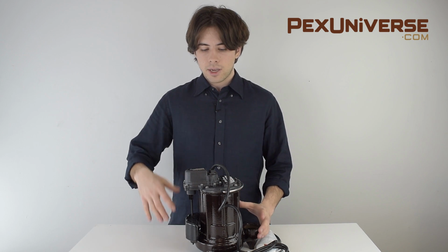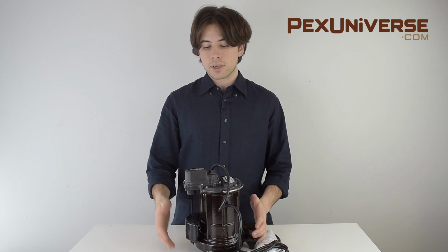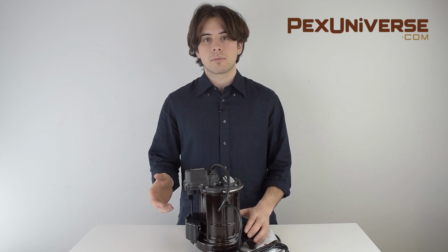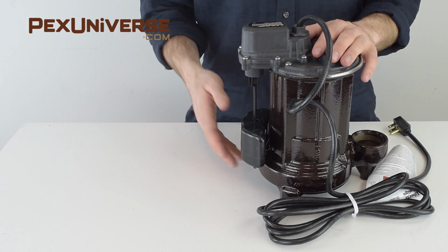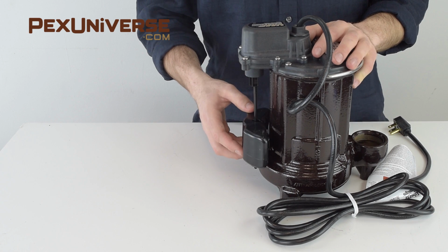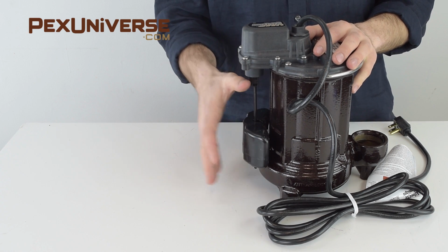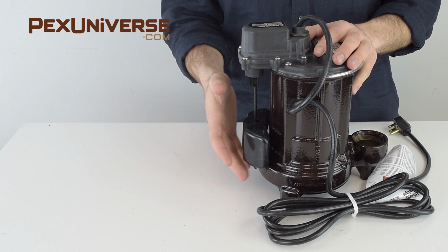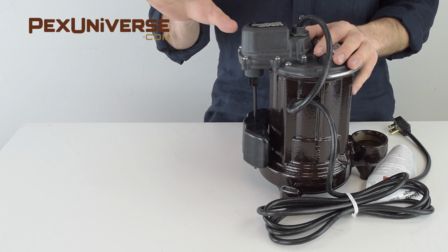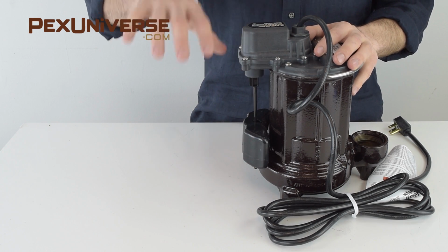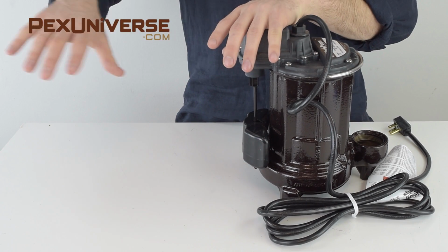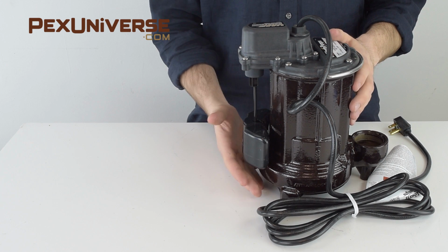Since this float only moves straight up and down, it can operate in a very narrow sump pit, and when you're working with a very narrow sump pit, it's going to fill up with liquid more quickly, so this is going to be on and off all the time, which means there's less cool-off time between cycles. So this is a vertical switch, but tethered and wide-angle switches float at an angle when water enters the basin to activate the pump. It'll go up just like this, and the pump turns on when the bulb is nearly straight up and turns off when it's straight down.